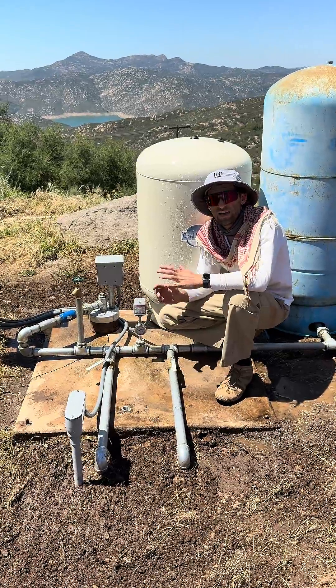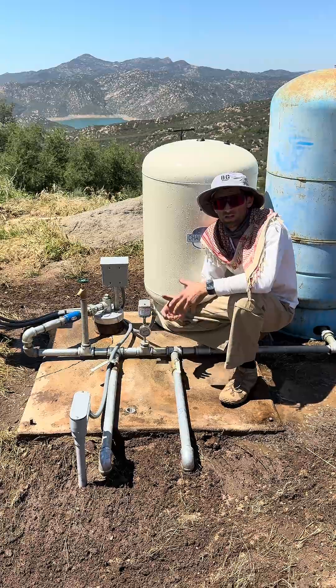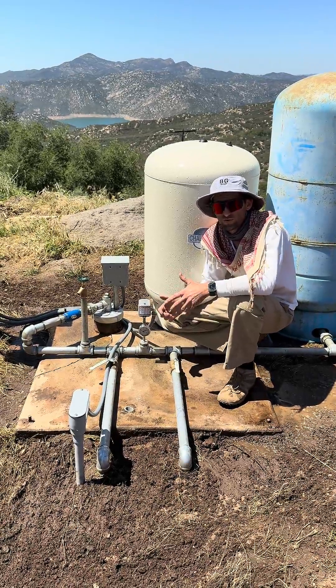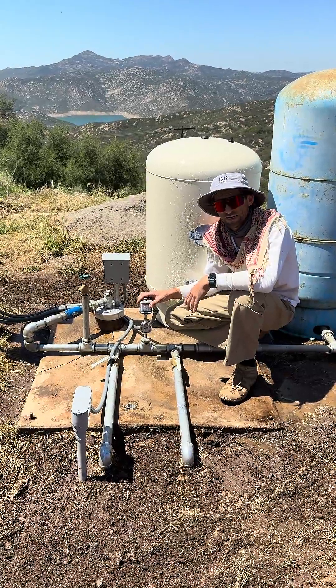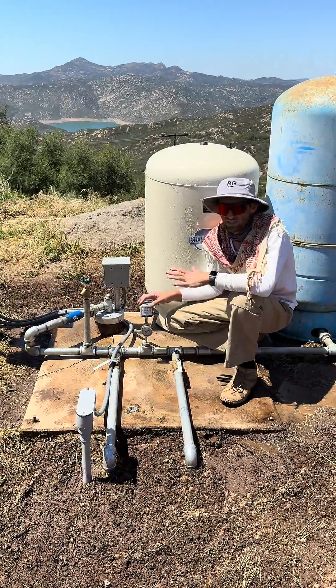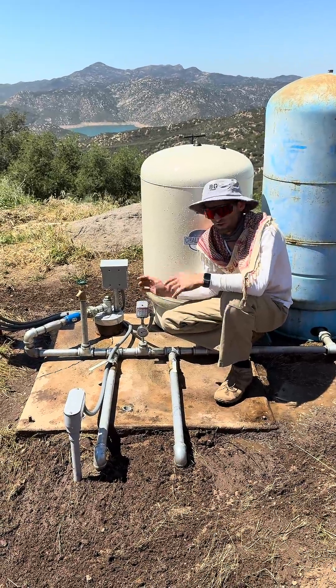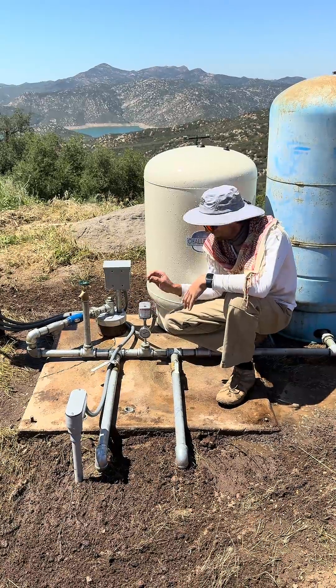Today we're showing how to clear a pressure switch. A lot of the times when your submersible pump or your booster pump fails to start, it's just the pressure switch that has some ants in it. I like to tell every customer who owns a well or a booster pump: if you have a pressure switch, you need to know how to clear it.